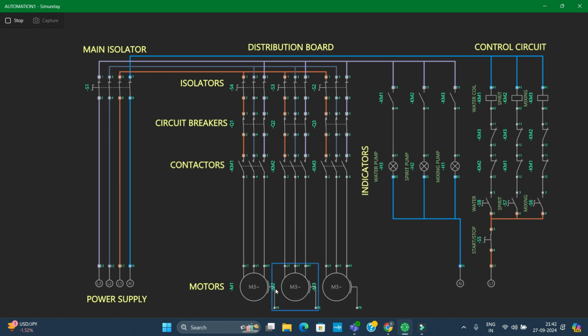So if you want to pump the water, you go to the water pump switch, right here. Take a look at these two normally closed contacts. Once I press the water pump switch to go on, the two of them open up. That means even if I close here or here, no other pump is going to turn on. That's the use of interlocking.